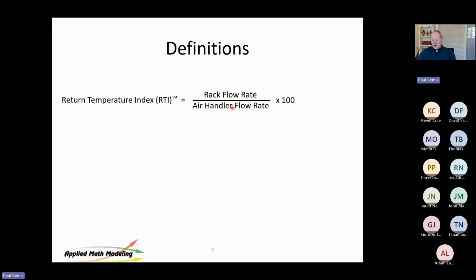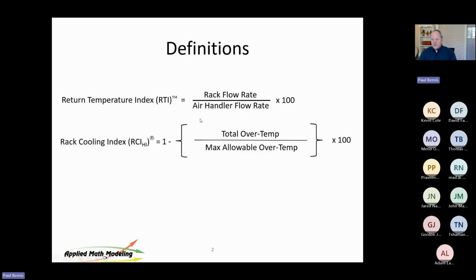If this number is bigger and you're contained, then you'll have a positive pressure differential between the amount of air being supplied and the amount of air being consumed by the racks. That's the goal, is to have a positive pressure differential across the rack. So the air goes in on the front and goes into the return system. Times 100 equals RTI. So you can see you want your RTI less than 100, right? Because if this number is bigger than that one, you're going to have a decimal times 100. You want it less than 100. If it's greater than 100, you've got pressure problems.